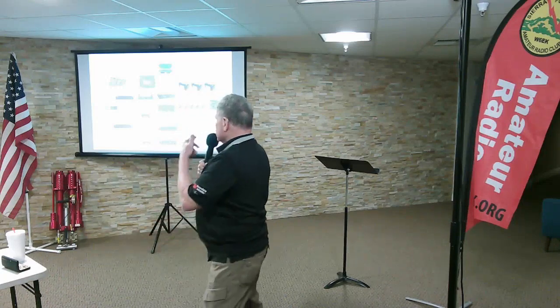You mentioned the batteries dropped to 0 below 12 volts. Is that because the battery management system shuts them down so there's no damage to them? The batteries themselves do this. The batteries are amazing. These Bioenno batteries and a lot of the lithium iron phosphate batteries have internal circuitry in them to shut them down. If they get to a certain point, they just shut off and say, I'm out of here. It's called a BMS, yeah. Right, battery management system.